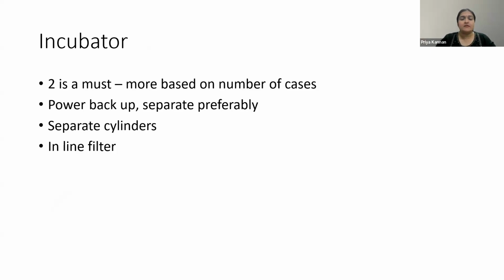For every incubator, it is recommended that you have a separate power backup in the form of a UPS, so that if one UPS goes off and you don't have power supply, and your two incubators are separate entities, then you can shift all the embryos and the gametes from one incubator into the working incubator. If all your incubators are connected to one single UPS, then if the UPS goes off, all your incubators are gone. It is also recommended to have separate cylinders for each incubator.